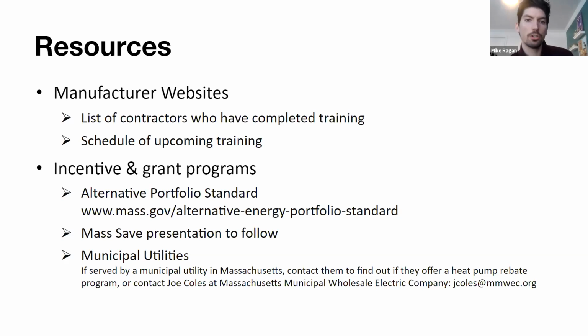So Beth asked a question: if you have hydronic for heat and forced air for AC, what is the best retrofit option? Obviously, with that alone, neither Alex nor I would just go right into an answer and say, this is the best response, just because every building's different, every application's different. But with the information you've given here, we have existing hydronic for heat. If it's a functioning system, it's a good legacy system, building owner is interested in keeping that online, that's perfectly fine. We could keep that on there, stage that ideally as our second stage of heat.